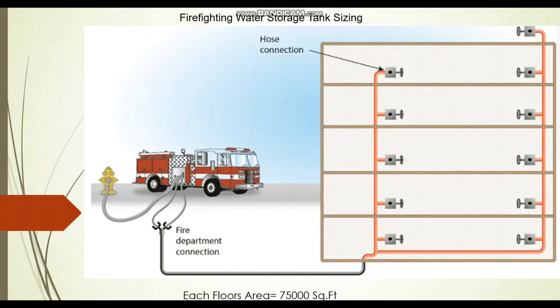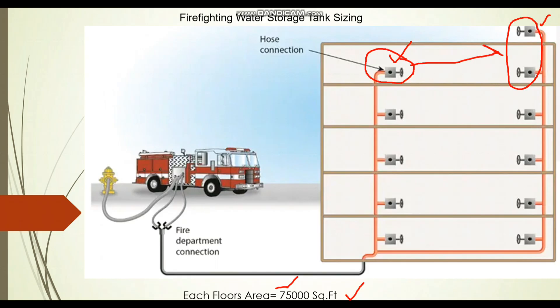Coming back to our system: we have 500 GPM from the remotest standpipe. For the next standpipe, since each floor area is 75,000 square feet — not exceeding 80,000 square feet — we consider only one landing valve at 250 GPM. So the total fire pump flow for our project is 500 GPM plus 250 GPM, giving 750 GPM as the fire pump size.